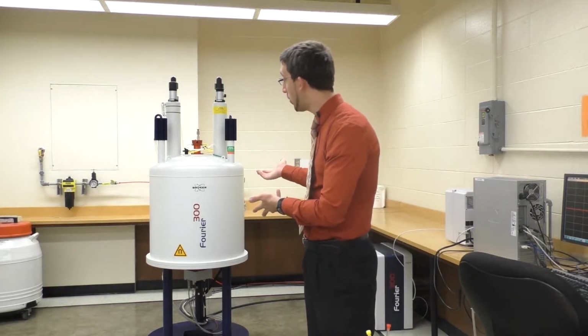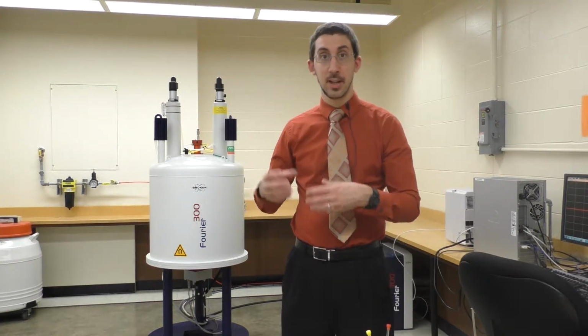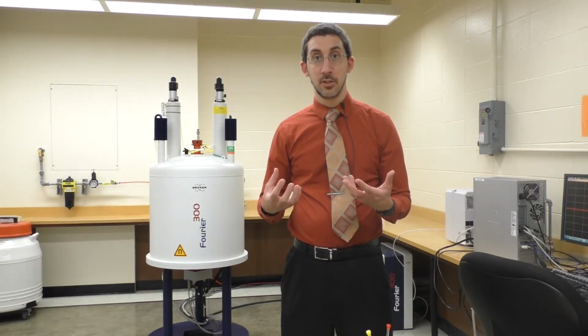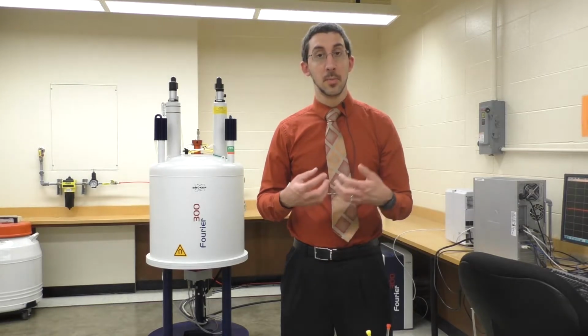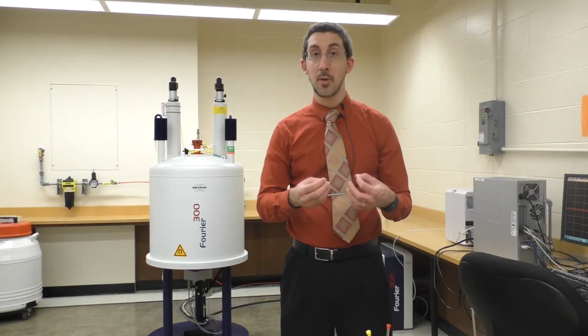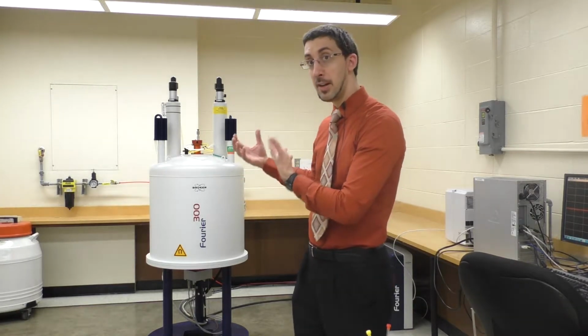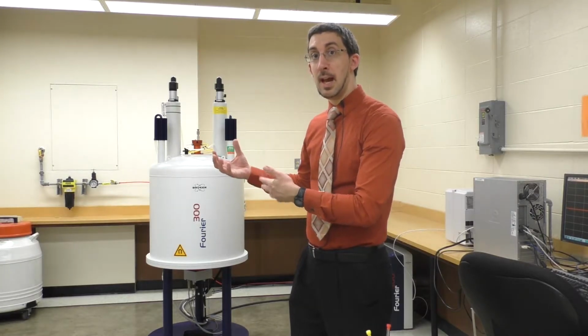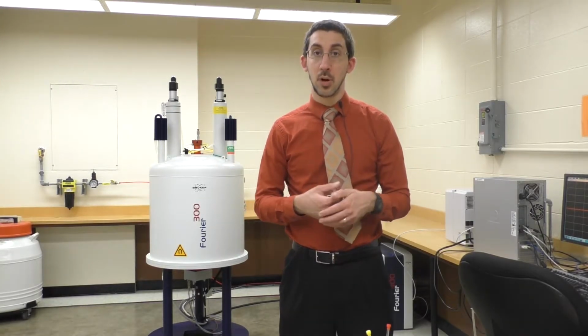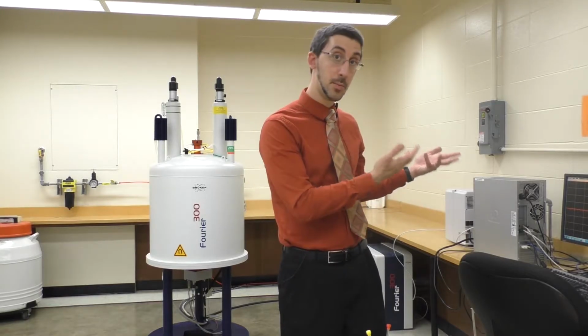Okay, so here we are in the NMR room. We're in front of the NMR spectrometer, which is a super-cooled superconducting magnet that's cooled by liquid helium, and then liquid nitrogen keeps the liquid helium cool. And what I'll show you in just a moment is how to prepare your sample, the NMR tube, to be able to be injected into the spectrometer. And then in the next video, I'll show you how to acquire the spectrum using the software on the computer.